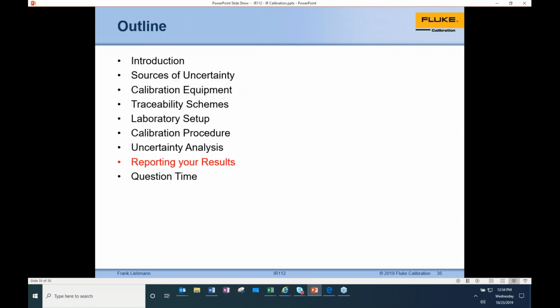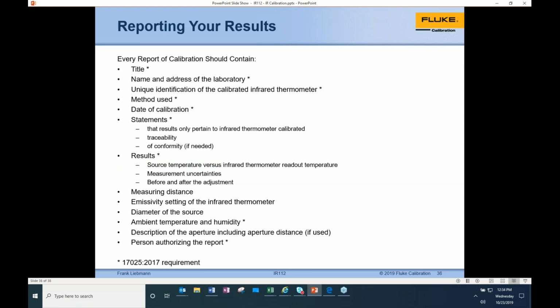Now we're going to jump to reporting your results. This is basically what's required once you've done the testing and compiled the data. For most reports, you're going to have a title, name, address, a unique identification number for the thermometer and your sources, and the method used. This goes back to scheme 1, scheme 2, obviously a date of calibration, and statements. If there are any exceptions, say for one of our calibration reports, we have statements about guard banding and K equals 2. There's a lot of different things you can touch on in your report if you think they might be a questionable point to be argued.